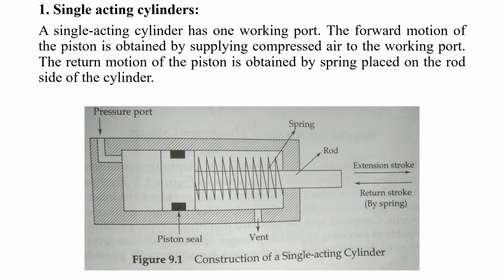Depending on how much output force you require, you need to design the diameter of this piston and the air pressure. The product of these things will give the force. So for that reason you should calculate how much pressure you should apply and what the piston diameter should be, depending on how much force you require. This is your actual single acting cylinder working principle.